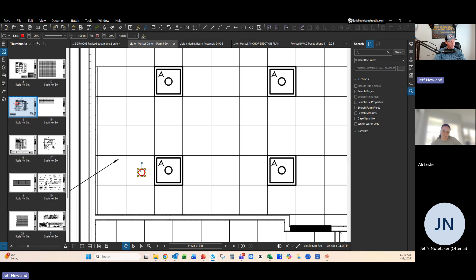Diffusers, you prefer that they match the drawings because they're going to be drawn. So if these were diffusers and not lights, you can see how they're all lined up here in the center of the room. The other reason that's important is because if these are supplying air, the calculations for how it's supplying that room have been determined by where it's located. So obviously, if a diffuser is supposed to supply air here in the center, but for whatever reason they've put it over here, that's a problem.